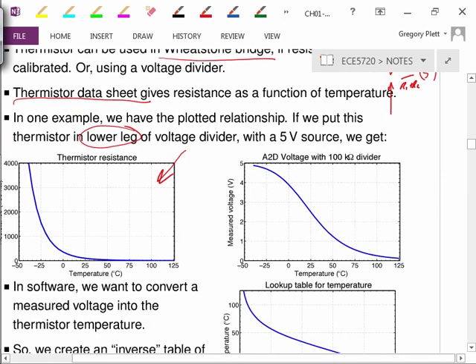So with that resistance plus the 100 kiloohm, I can evaluate the mathematical expression that computes the voltage input to the analog to digital converter as a function of temperature, again going from about -50 up to about 100 degrees Celsius, and we get a function that says measured voltage from 0 to 5 volts corresponds to some temperature. So if I measure 3 volts, I'd go across and down and say that's more or less 20 degrees Celsius, although we could figure it out more accurately.